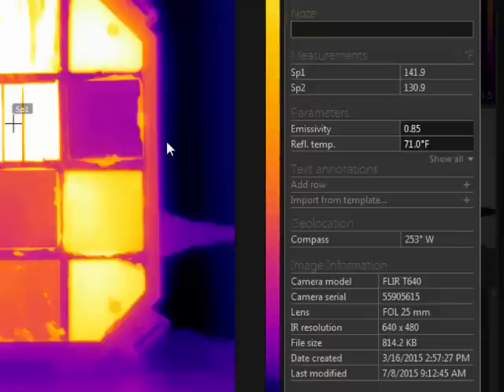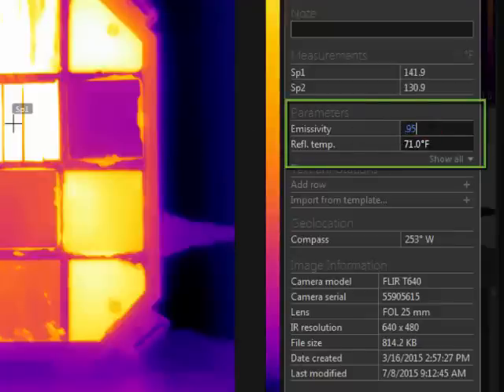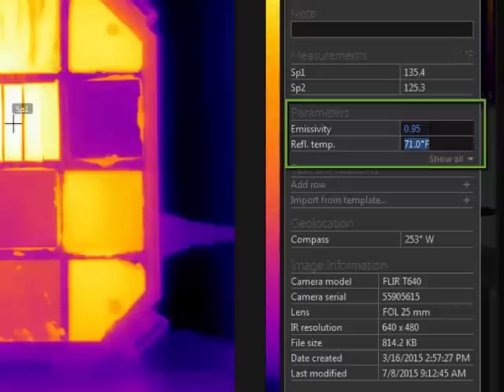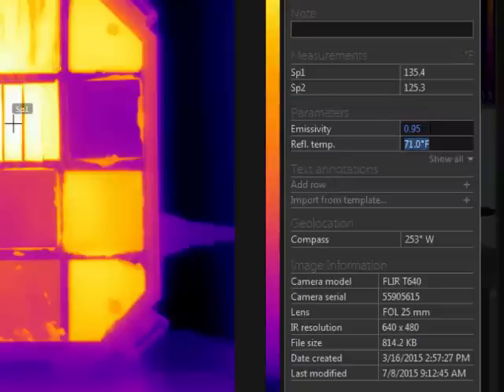Object parameters, like emissivity and reflected temperature, can be adjusted here. If something is changed, the measurement results will update globally.